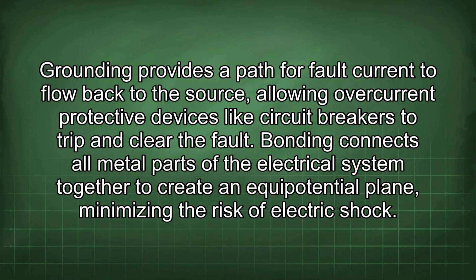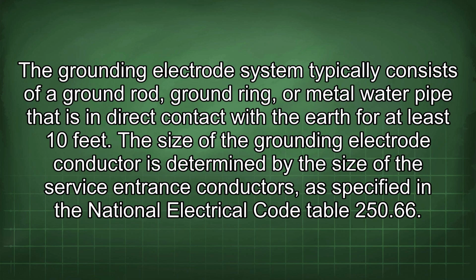Bonding connects all metal parts of the electrical system together to create an equipotential plane, minimizing the risk of electric shock. The grounding electrode system typically consists of a ground rod, ground ring, or metal water pipe that is in direct contact with the earth for at least 10 feet.